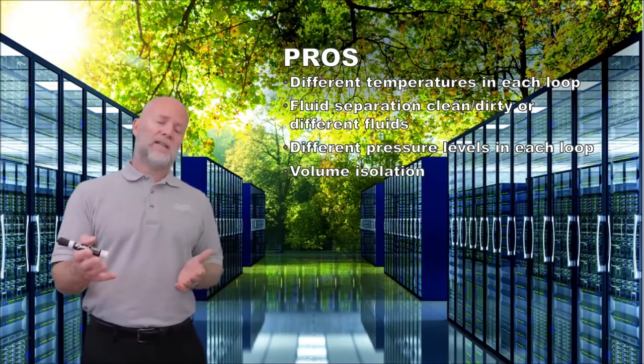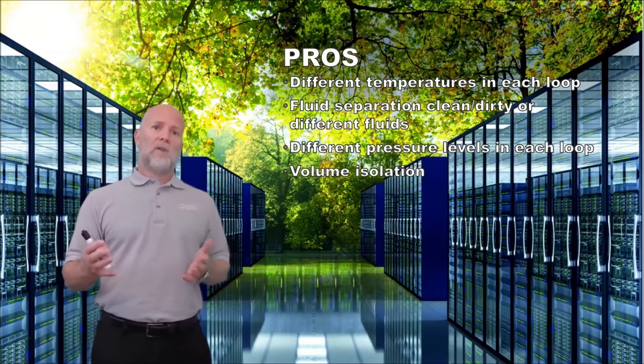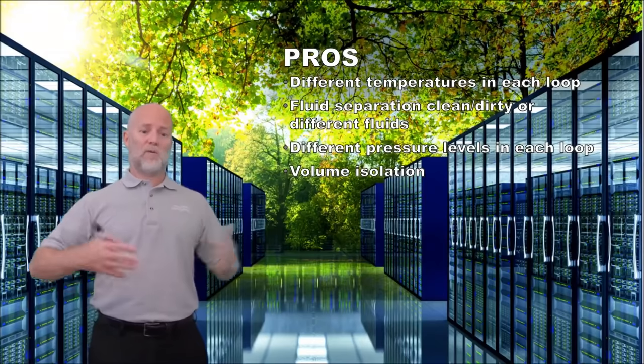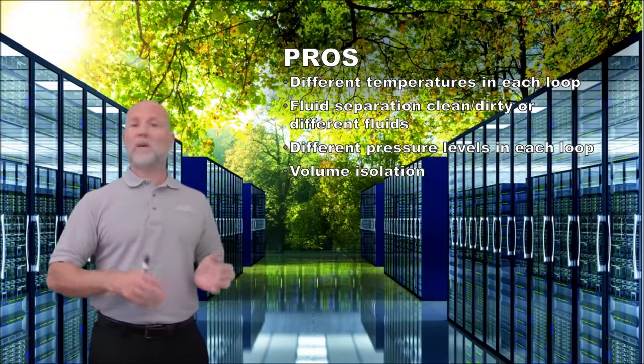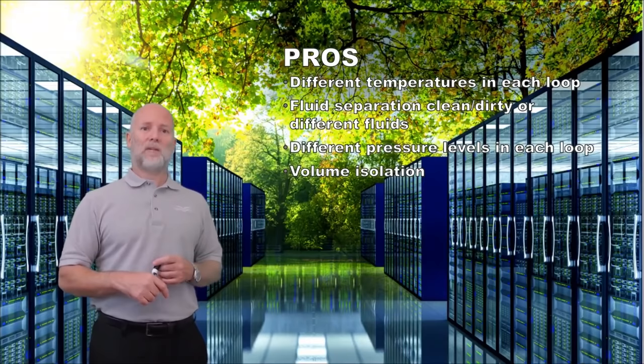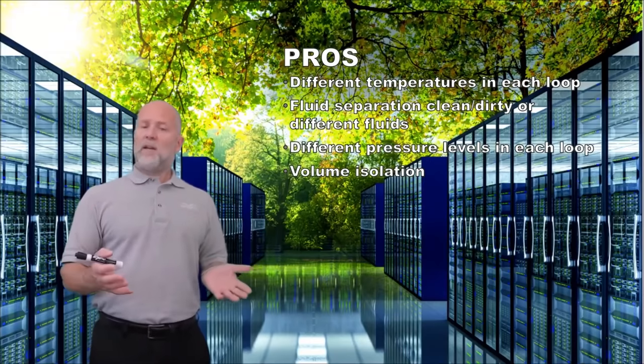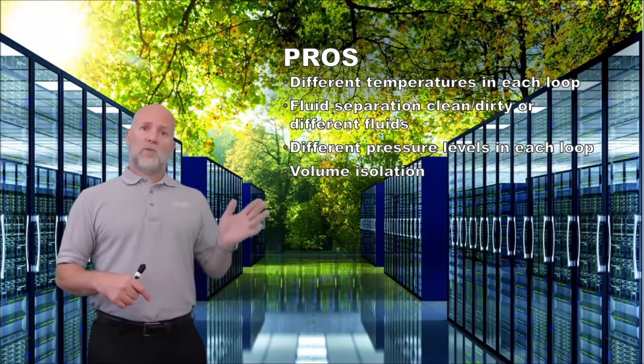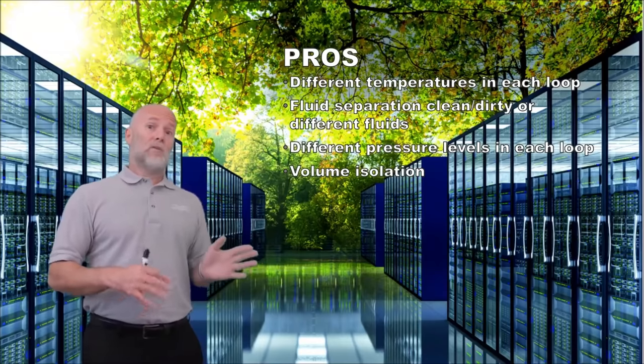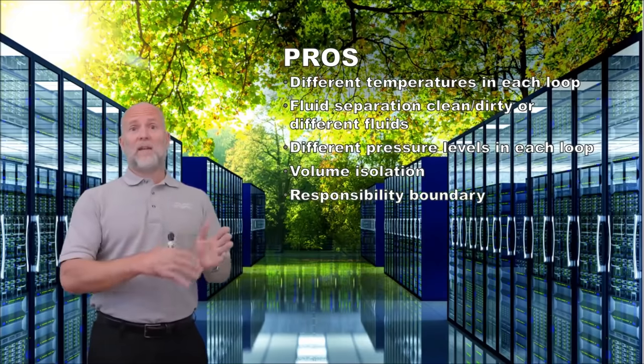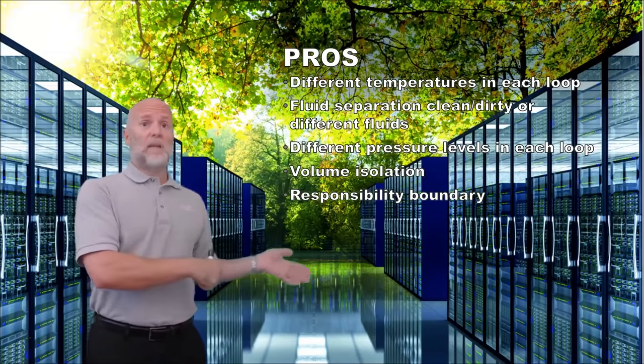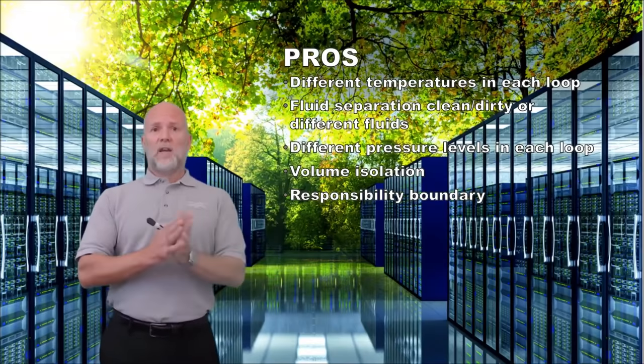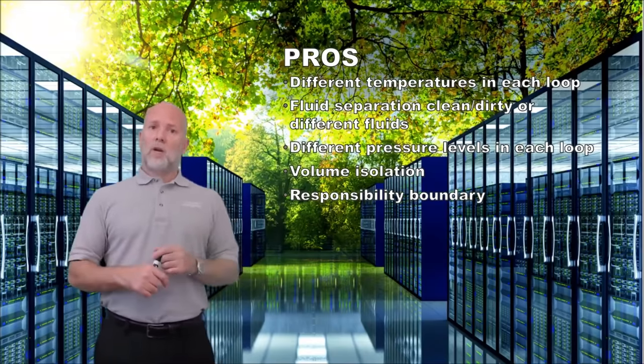Think about if you are in a seismic area and you have a tremor — all those joints might leak, and if you have a 24-inch pipe inside your server room, it's a situation you maybe don't want to experience. And if you are in a colocation environment, the heat exchanger is a clear service level agreement boundary, where the responsibility of one side ends and the responsibility of the other side begins. Those are the advantages of decoupling your cooling system.